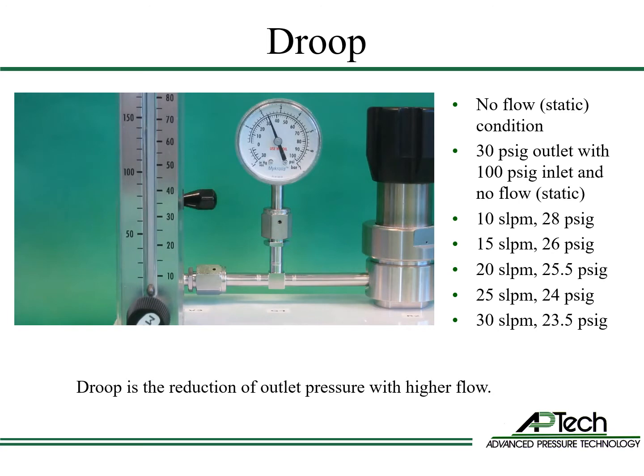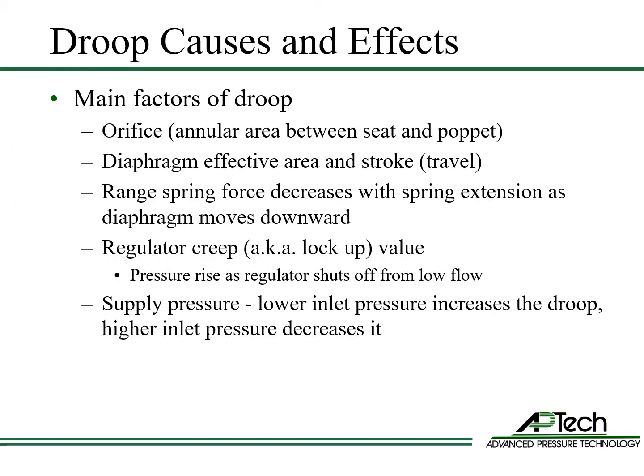This reduction in outlet pressure with higher flow is called droop. Regulator droop is caused by several factors. A larger orifice, diaphragm, and diaphragm stroke reduce droop. The adjustment range spring's force decreases with spring extension as the diaphragm moves downward, which increases droop. When a regulator transitions from low flow to no flow, the regulator creeps or locks up, and the outlet pressure increases slightly above set point, increasing droop. Finally, higher supply pressures decrease droop, and lower supply pressures increase droop, as we will demonstrate in the next slide.